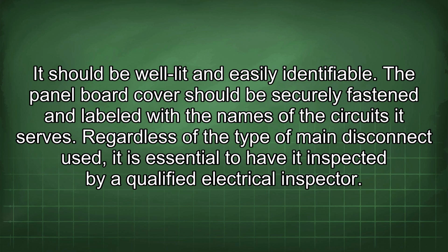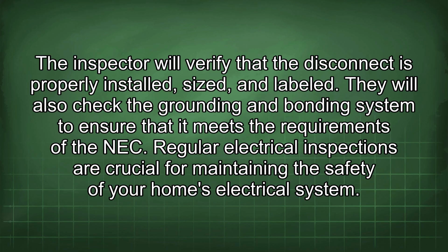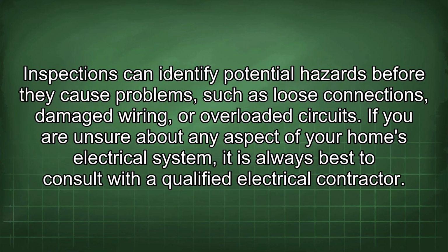Regardless of the type of main disconnect used, it is essential to have it inspected by a qualified electrical inspector. The inspector will verify that the disconnect is properly installed, sized, and labeled. They will also check the grounding and bonding system to ensure that it meets the requirements of the NEC. Regular electrical inspections are crucial for maintaining the safety of your home's electrical system. Inspections can identify potential hazards before they cause problems such as loose connections, damaged wiring, or overloaded circuits.